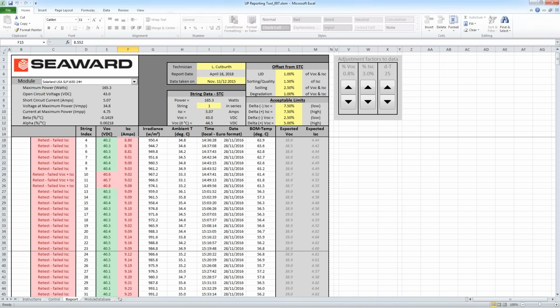Oh, one more question here. How can you determine if the string has PID? Good question, Christina. The answer there is what I mentioned about our expected values compared to our measured values. So if we're expecting 800 volts, for instance, and we only get 600 volts, okay, then that indicates to me that there is an issue. That's why it's really important that we get good temperature data if we're looking to analyze what the VOC should be with regard to our expected values and with regard to STC.